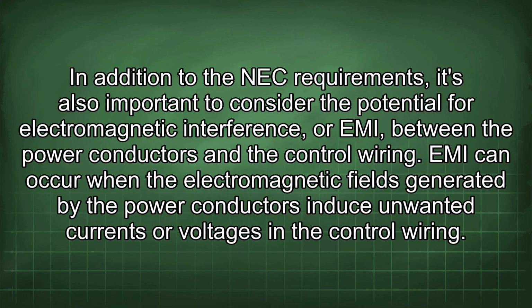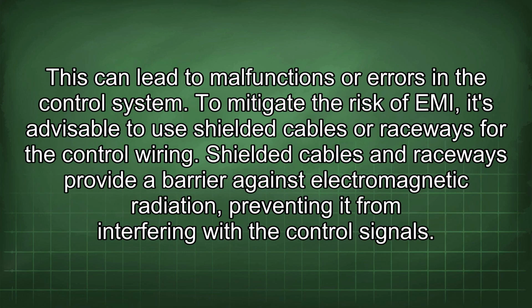In addition to the NEC requirements, it's also important to consider the potential for electromagnetic interference, or EMI, between the power conductors and the control wiring. EMI can occur when the electromagnetic fields generated by the power conductors induce unwanted currents or voltages in the control wiring. This can lead to malfunctions or errors in the control system. To mitigate the risk of EMI, it's advisable to use shielded cables or raceways for the control wiring. Shielded cables and raceways provide a barrier against electromagnetic radiation, preventing it from interfering with the control signals.